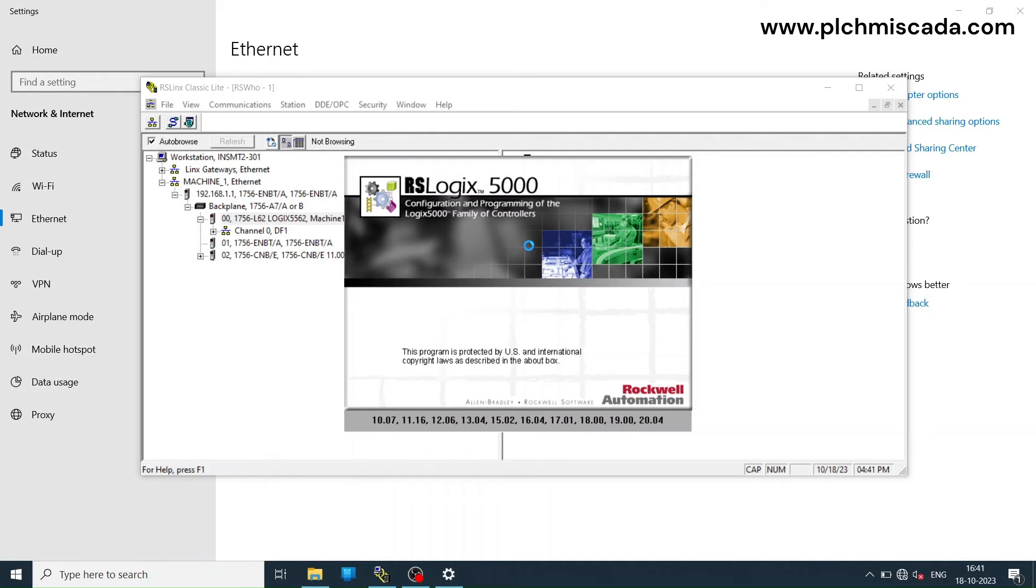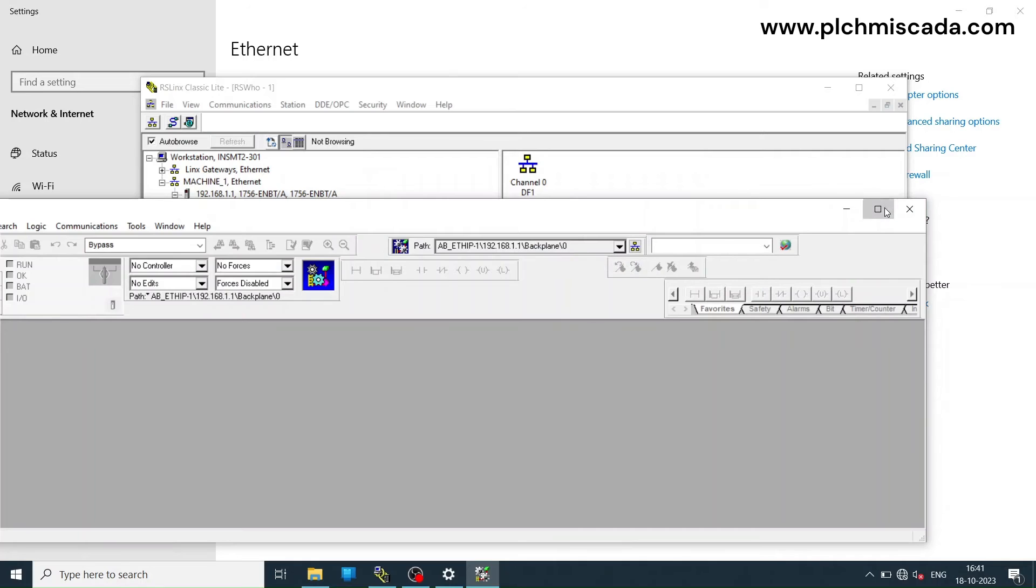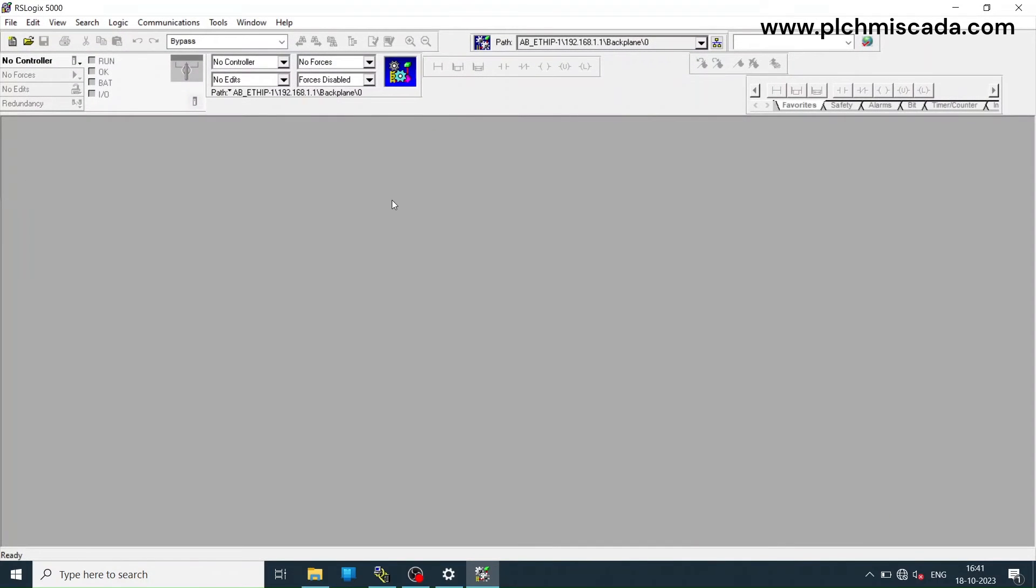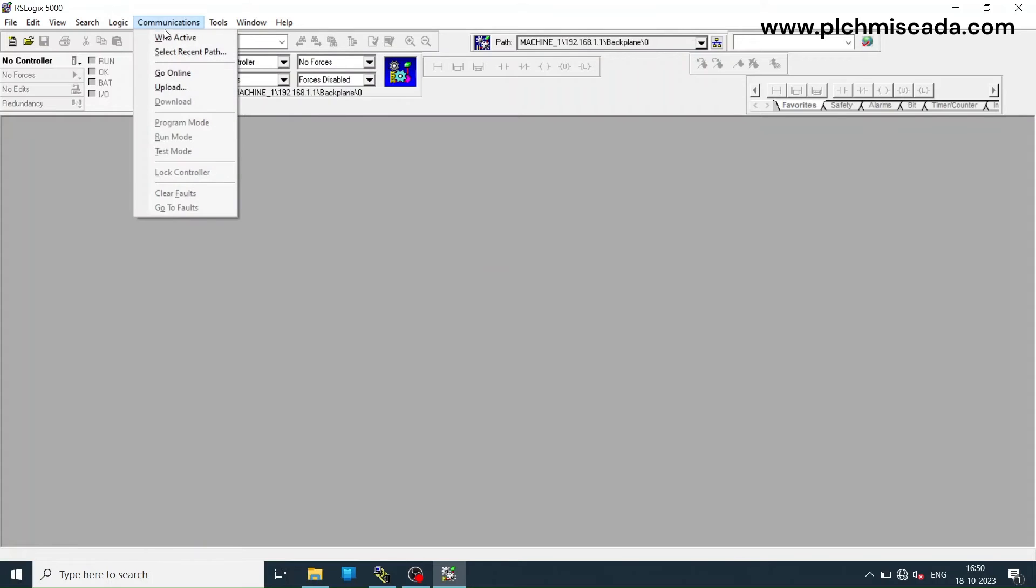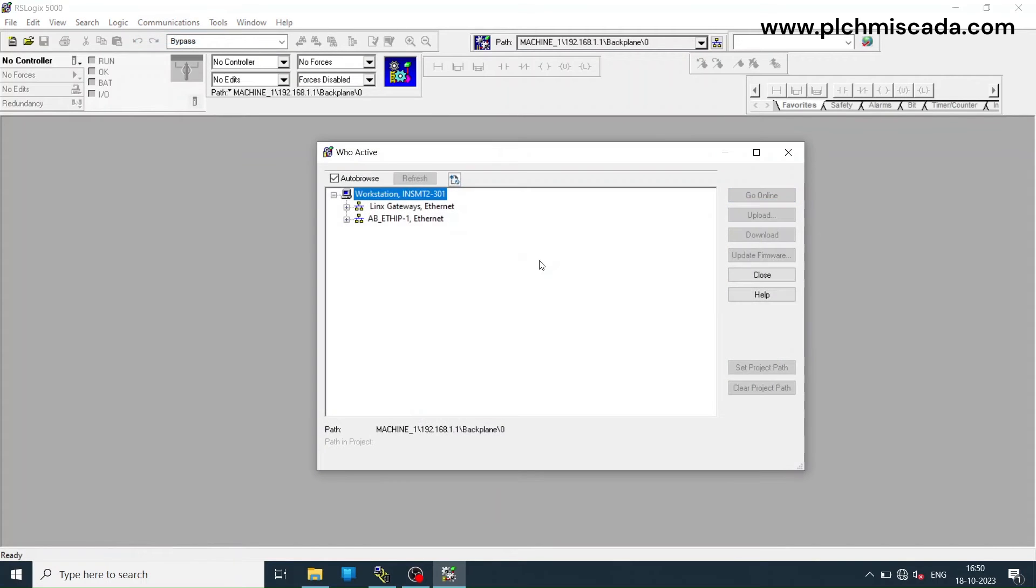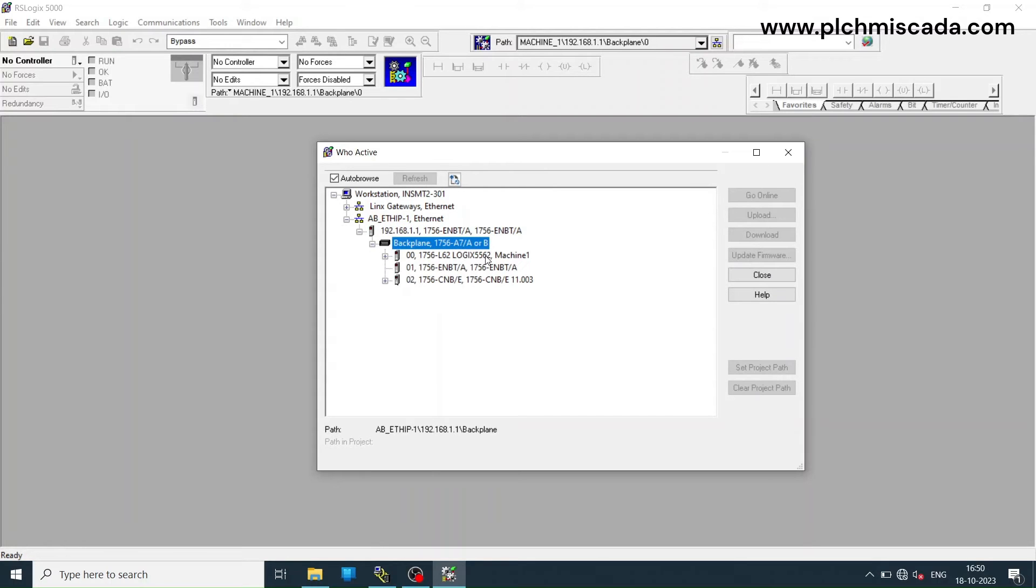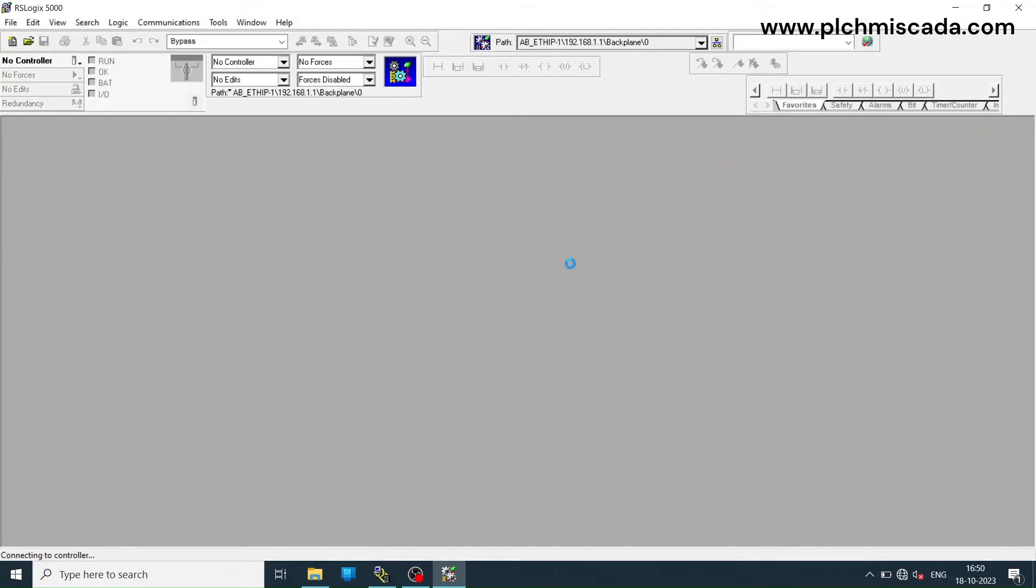Now open RS Logix 5000 software. Go to communication tab and select who active. Browse the Ethernet IP adapter and select the PLC. Select the upload option.